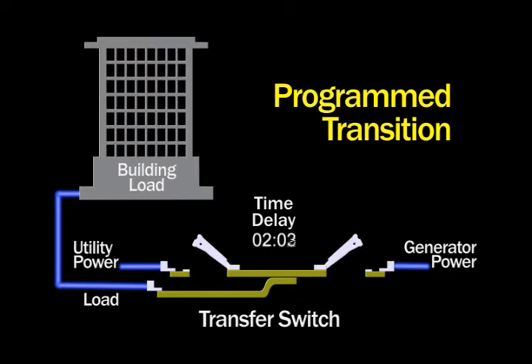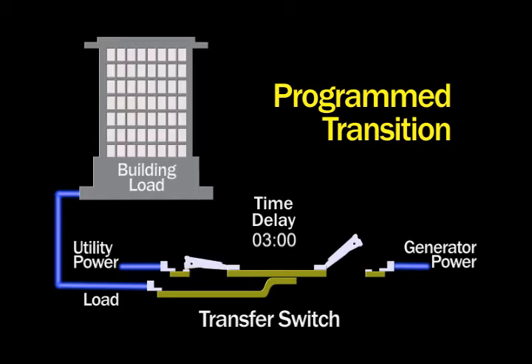Programmed transition mode adds a time delay to pause the transfer switch in the center off position. This allows time for motor voltages to decay before connecting to an out-of-phase power source, which could potentially damage the motors.